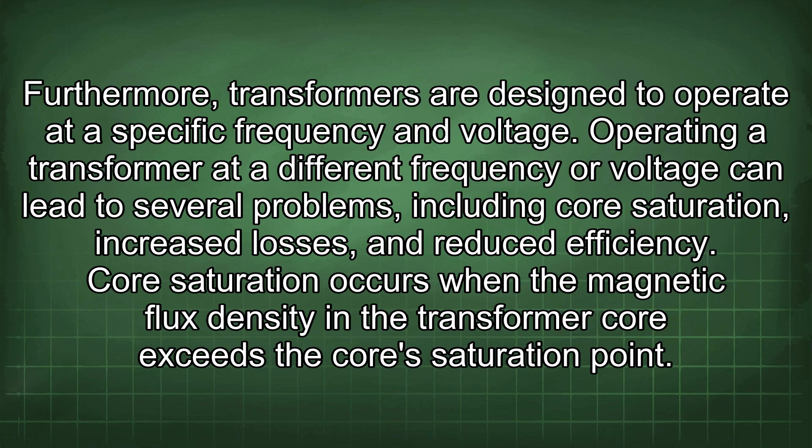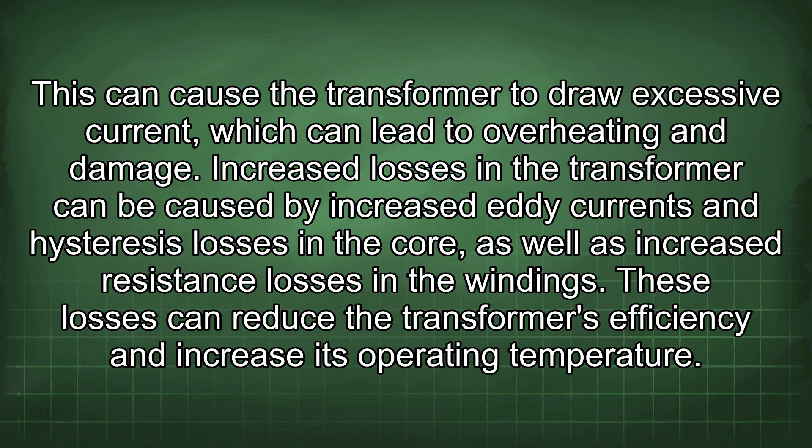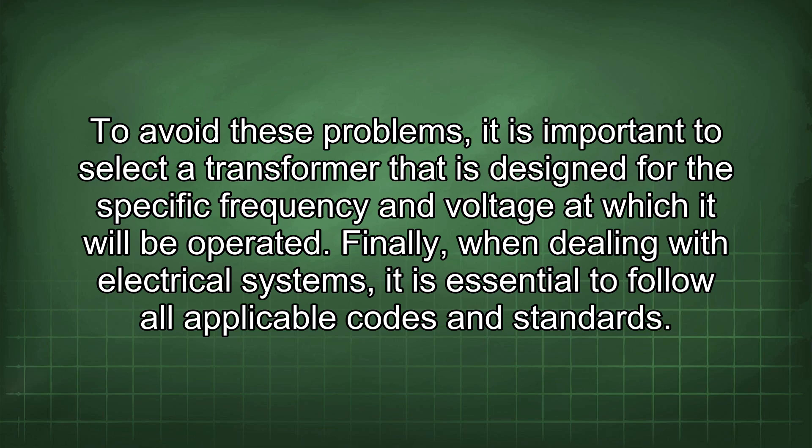Furthermore, transformers are designed to operate at a specific frequency and voltage. Operating a transformer at a different frequency or voltage can lead to several problems including core saturation, increased losses, and reduced efficiency. Core saturation occurs when the magnetic flux density in the transformer core exceeds the saturation point, causing the transformer to draw excessive current which can lead to overheating and damage. Increased eddy currents, hysteresis losses, and resistance losses in the windings can reduce efficiency and increase operating temperature. It is important to select a transformer designed for the specific frequency and voltage at which it will be operated.